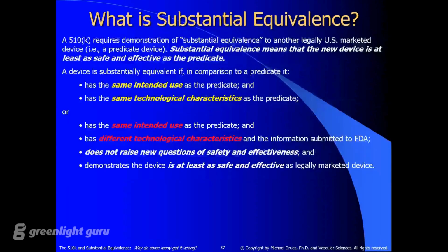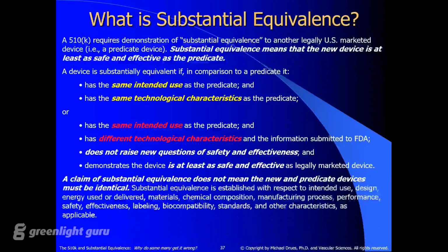In other words, it has to be at least as safe and effective as the predicate device. A claim of substantial equivalence does not mean that the new and the predicate devices are identical, and that's an important point. And now this comes to one of the most fundamental questions that the medical device industry has been struggling with since the 510K was created in 1976, and that is, how different can two technologies or two different devices be, and yet still be similar enough, close enough to be substantially equivalent?